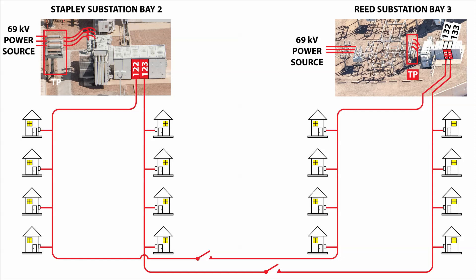Two transformer bays are shown at Stapley substation and at Reed substation, which are a few miles apart. Four single-phase 7.2 kV circuits will be used to illustrate how SRP restores power after a fault occurs. A fault is defined as any problem which causes electricity to flash phase to phase or phase to ground. All electrical circuits are insulated to guide electrical energy to the desired load, and when this insulation breaks down, we call the problem a fault and electricity flashes like lightning between two phases or from a phase to ground.